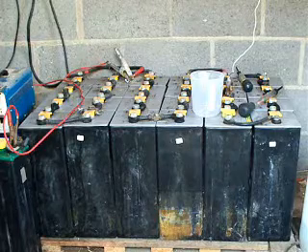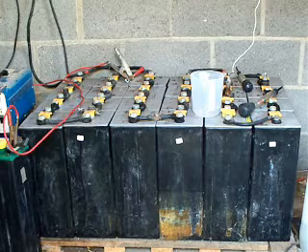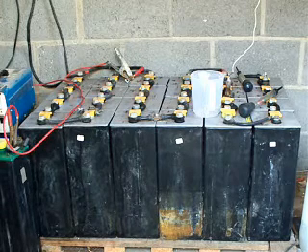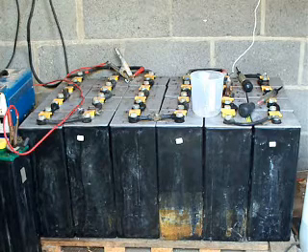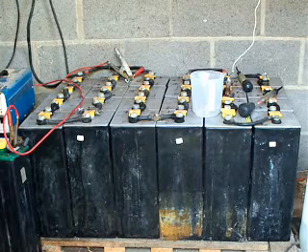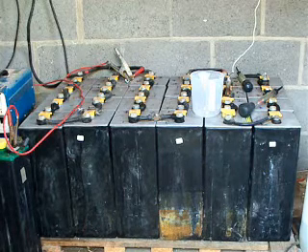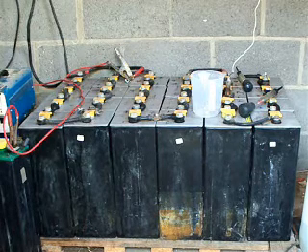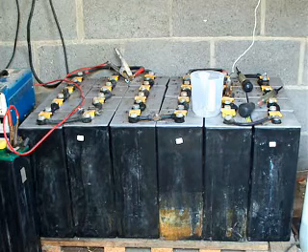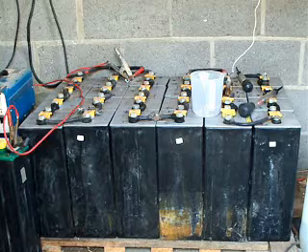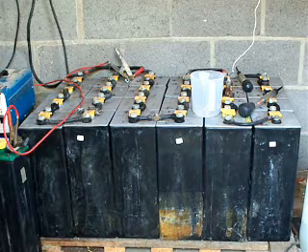This is the battery pack. In this case there are 24 600 amp hour cells wired in series to produce a 48 volt battery pack. That means each cell is a nominal 2 volts. If you wanted a 24 volt battery pack, of course, you would only have 12 of these cells. There is a 1 litre jug shown on the battery to give you some sort of scale.